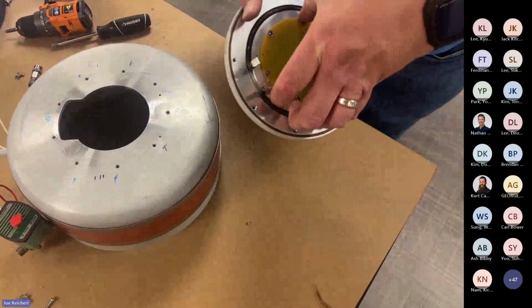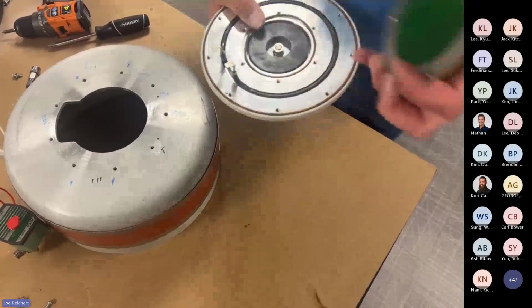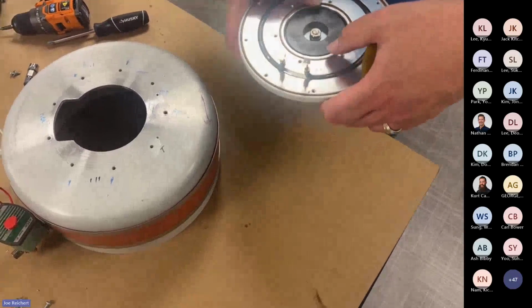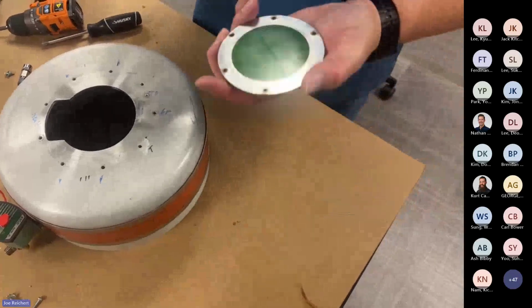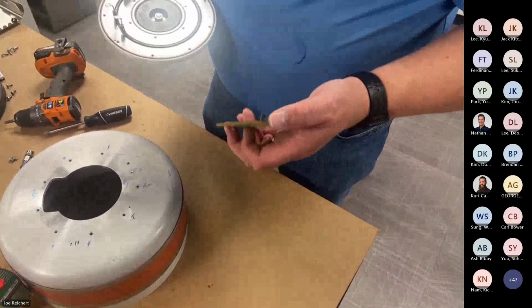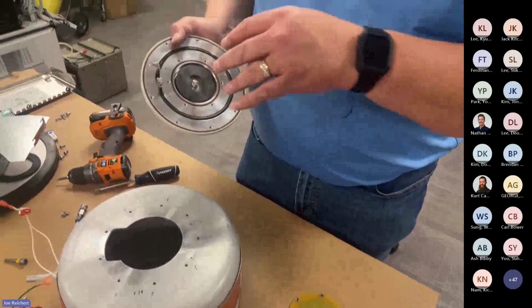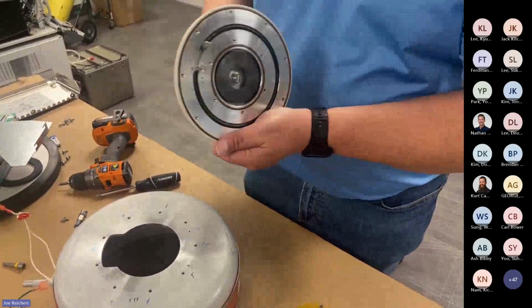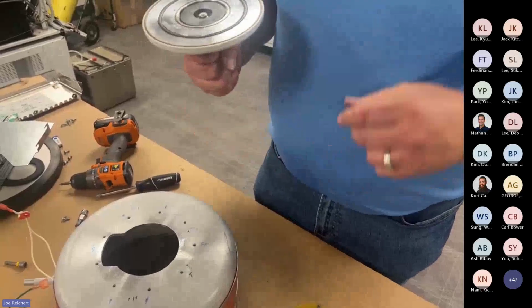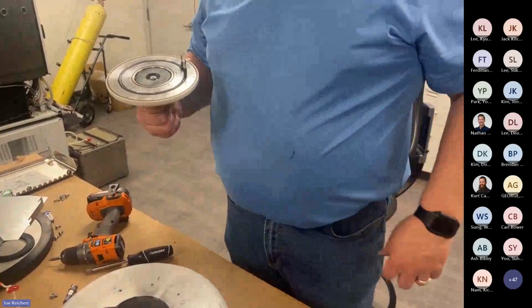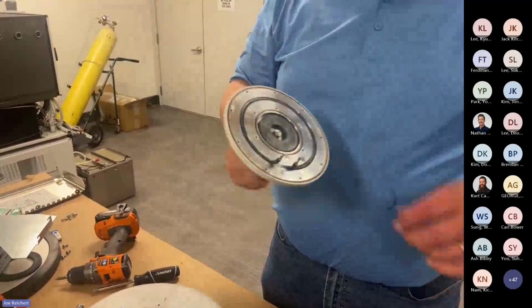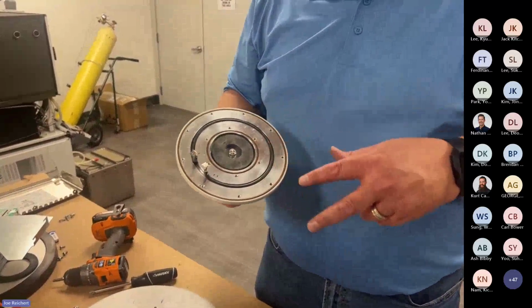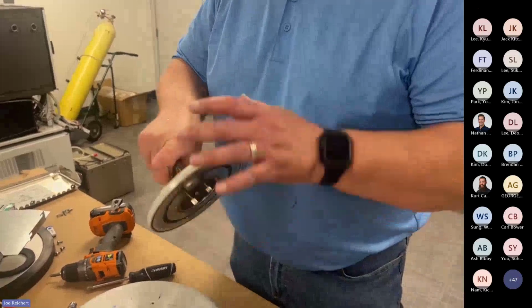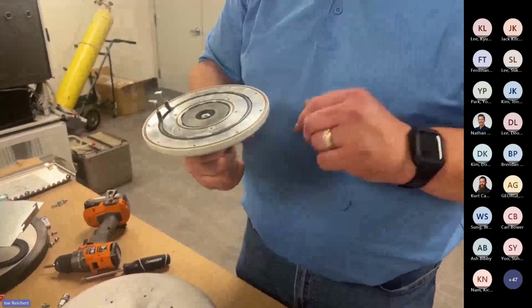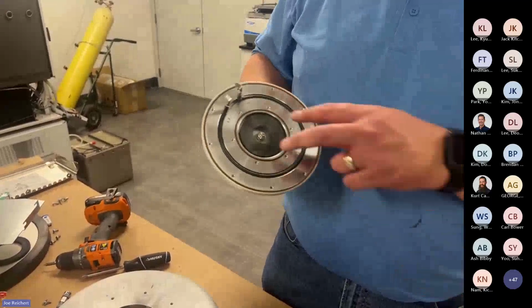There, the seal plate comes off, and has some vacuum grease underneath it too. These O-rings have vacuum grease on them. It's just a little plate with no metal inside it so that the magnet can work its way through it to get to the magnet on the bottom of the shaft. So if you end up with some bearings that are worn out and need to be replaced, you get this whole piece minus the heater and the O-rings. You do need to reuse those from the old unit. But you'll get this whole piece with the hub and the shaft, magnets already attached. This one just mounts straight to the bottom of it.